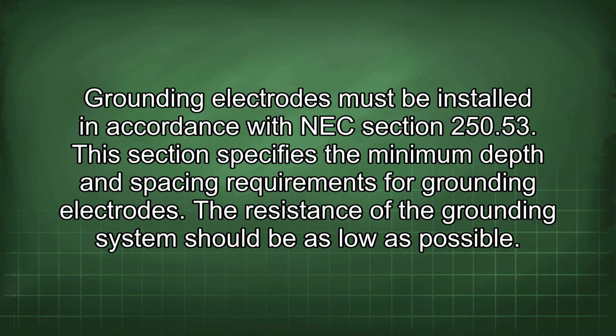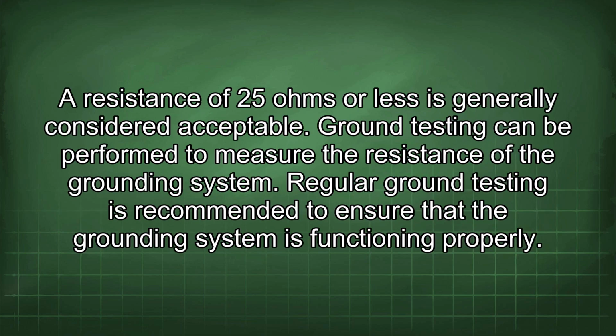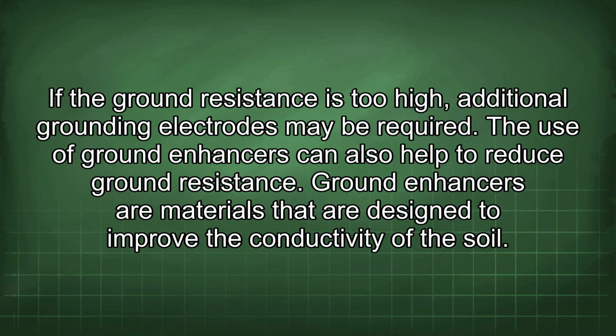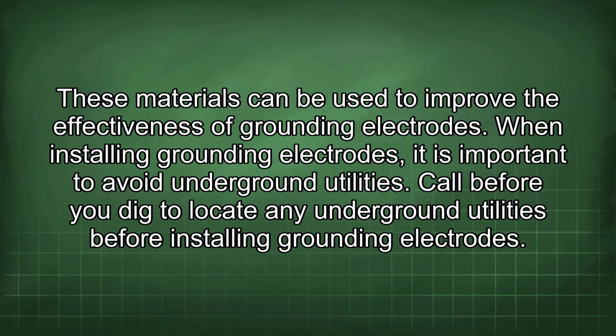The resistance of the grounding system should be as low as possible. A resistance of 25 ohms or less is generally considered acceptable. Ground testing can be performed to measure the resistance of the grounding system. Regular ground testing is recommended to ensure that the grounding system is functioning properly. If the ground resistance is too high, additional grounding electrodes may be required. The use of ground enhancers can also help to reduce ground resistance. Ground enhancers are materials that are designed to improve the conductivity of the soil. These materials can be used to improve the effectiveness of grounding electrodes.